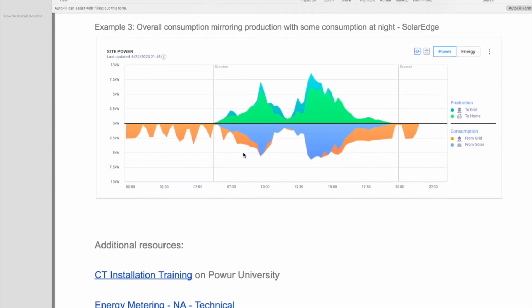And then lastly, this one's not as noticeable, but you'll see consumption looks normal. It's bouncing around at night from the grid. But then you'll see when the sun comes up, consumption spikes with solar production. When the solar production drops, the consumption drops. When the solar production rises again, the consumption rises again. And then once the solar goes down, it's kind of doing its own thing again, right? This is a clear sign of a CT installation error because consumption in the home and solar production have nothing to do with each other. There should never be any correlation between those two values.